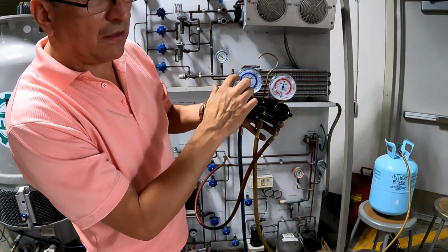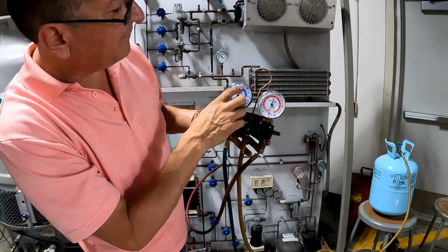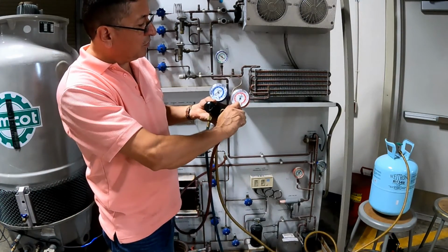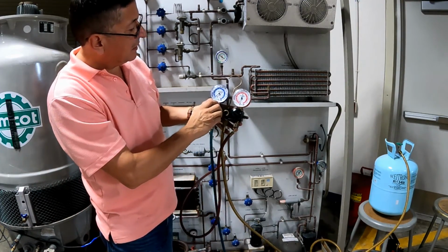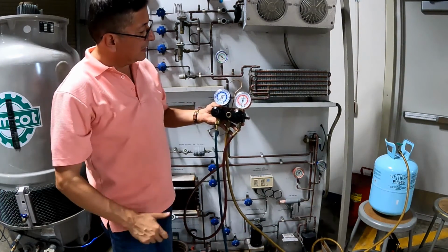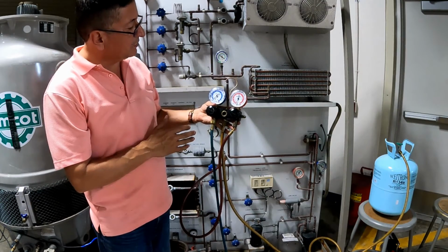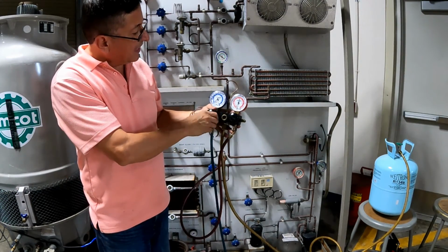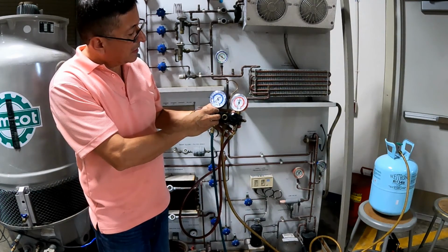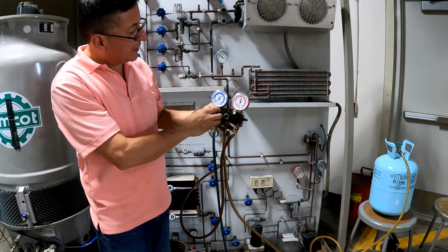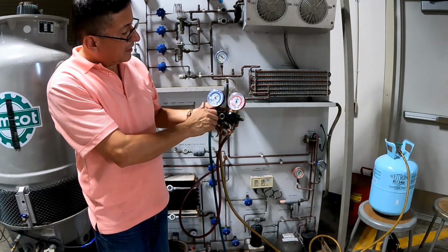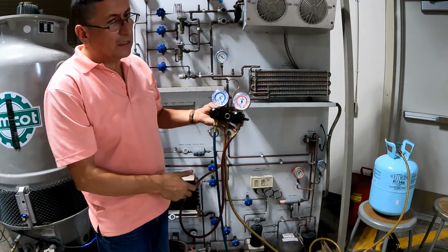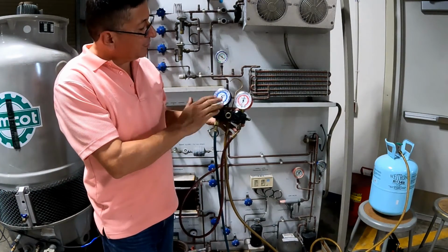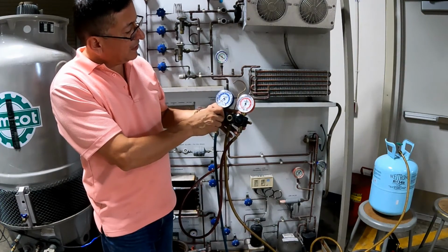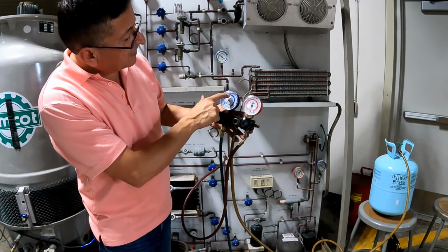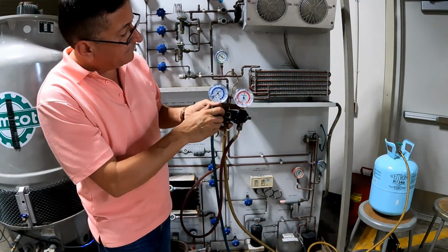In this moment it is in the blue scale, around 60-75. It's okay. And now we are going to open. We are going to close again. The system is 75, it's closed, it's good. We are going to open again. That's perfect. We are going to close again. The idea is to open and close until the pressure is stable. 70-80 psi is okay. It's 75. Remember, it's the blue scale.